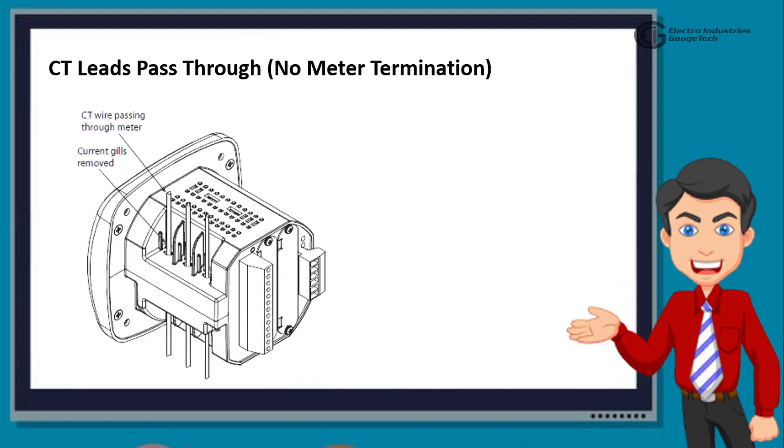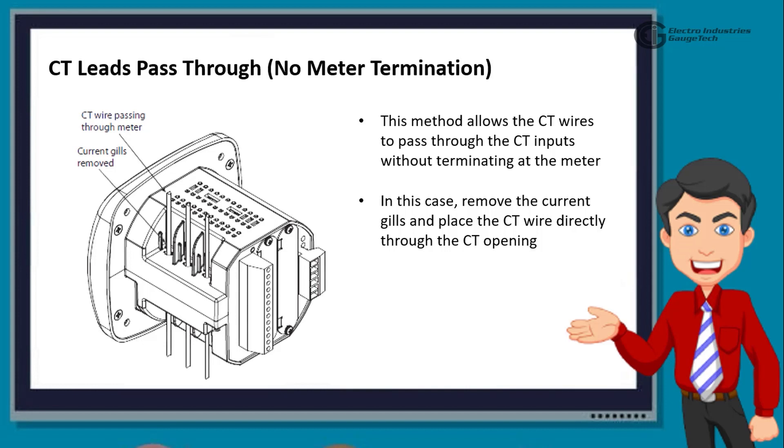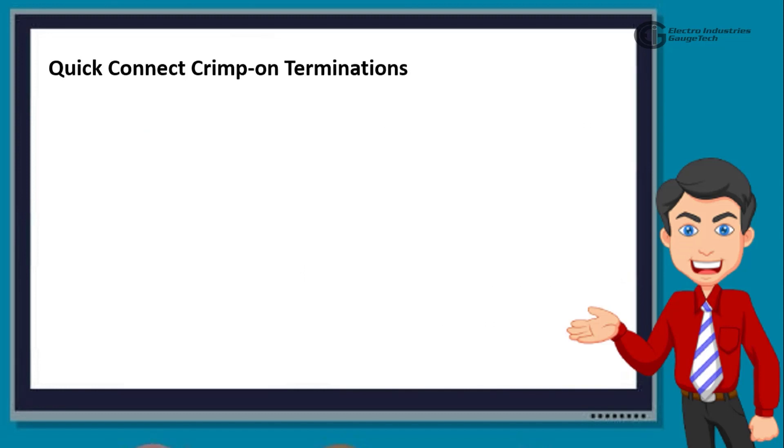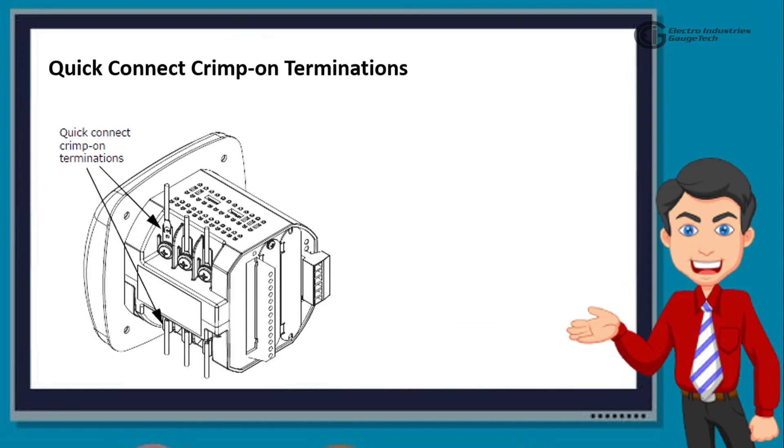We will look at other current connections along with voltage and RS485 KYZ connections and wiring diagrams later in this video. After this, we move to the next section, which is CT leads passed through no meter termination. This method allows the CT wires to pass through the CT inputs without terminating at the meter. In this case, remove the current gills and place the CT wire directly through the CT opening. The opening accommodates up to 0.177 inches or 4.5 millimeters maximum diameter CT wire. Next, we have the quick connect crimp-on terminations. For quick termination or for portable applications, 0.25 inches quick connect crimp-on connectors can also be used.